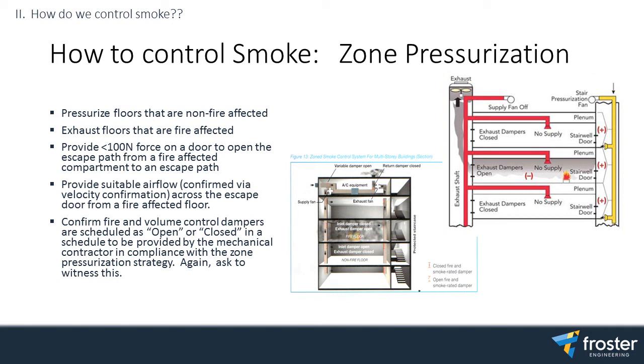Confirm suitable airflow across the door. I'll show you an image of that. So this is something you need to witness, and something I'll have to witness as well. When the commissioning agent's doing a smoke test, we want to make sure there's an average 1 meter a second across the escape path doors and the fire-affected floors when you're leaving that floor, to prove that you're getting a pressure differential, and also to make sure that there's no risk of smoke ingress into the other floors, into the escape stair.